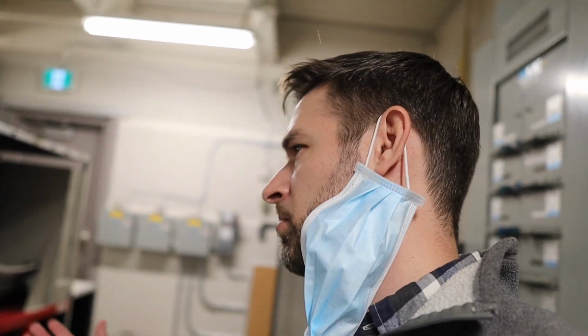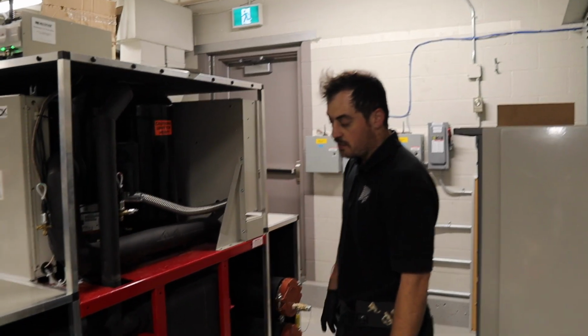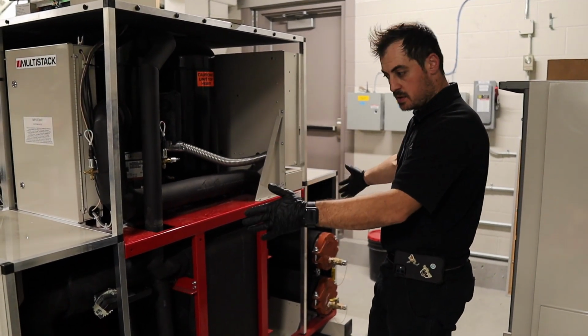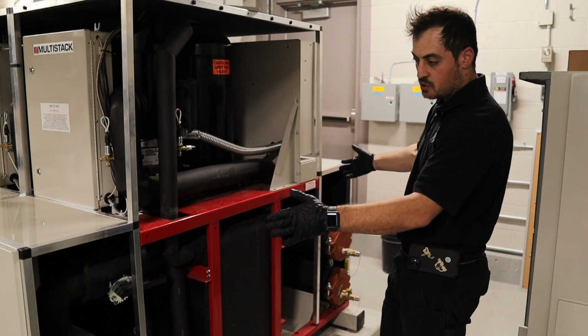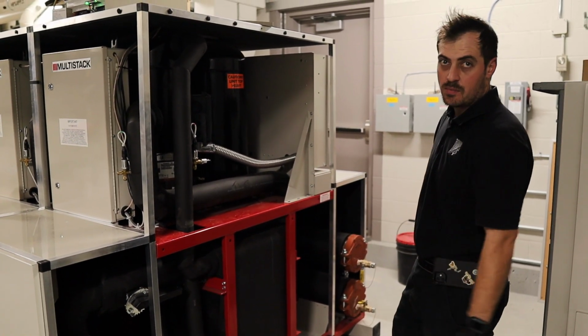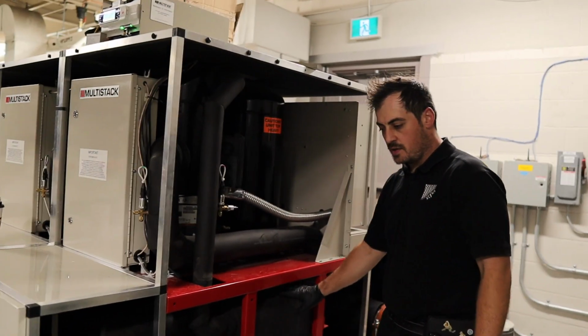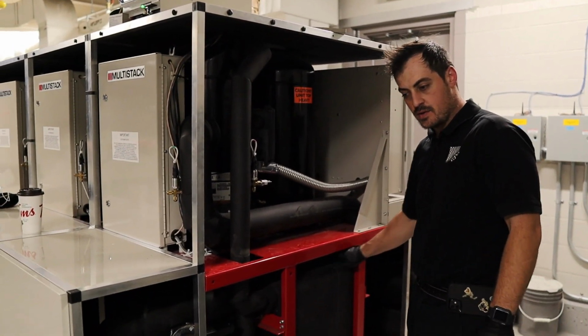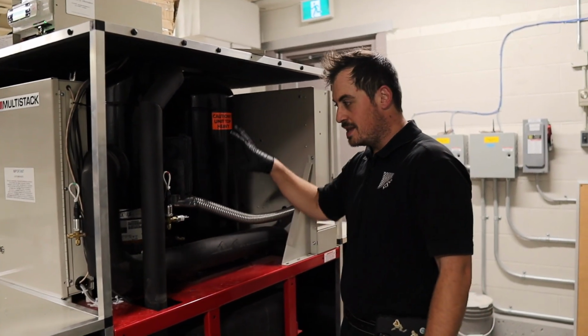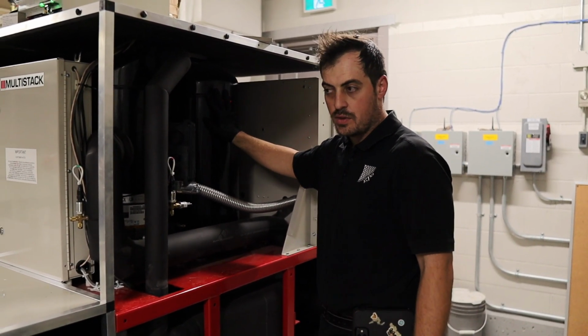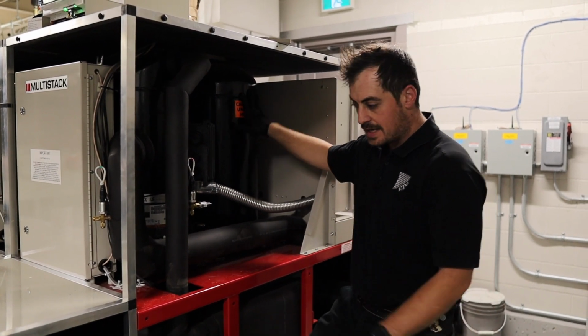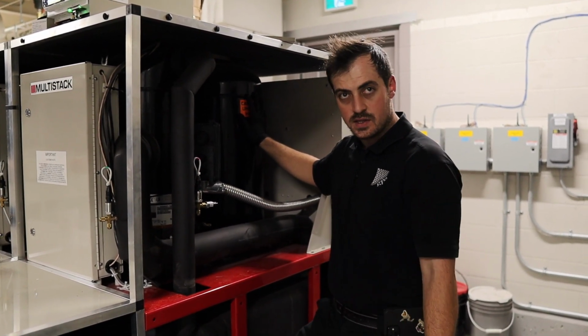Now, can you tell me just a little bit, what makes this chiller a heat recovery chiller? What's the definition basically of a heat recovery? Because this is kind of similar to a heat pump in some ways, but what's the difference between this and... With the heat pump, you can change this. The difference is from a regular circuit to a heat pump. Obviously, we have a 4-way valve that allows you to switch your evaporator and condenser back and forth depending on your operation mode. With a heat recovery, you're staying within a certain parameter that you're constantly heating. So in this case, this heat recovery chiller has the R-134a refrigerant in it that allows it to go to higher temperatures than a 410A system could.